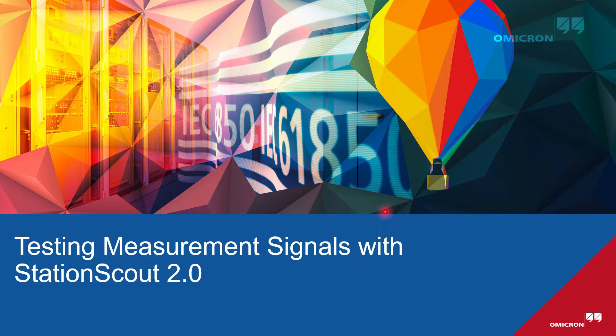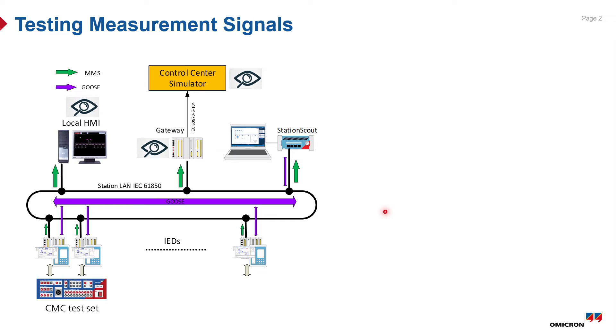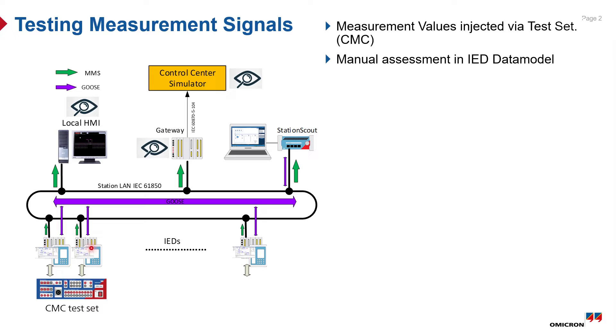First of all, let me explain the setup we are going to use. We have a CMC test set wired to an IED to inject analog measurement values. The measurement values received by the IED are represented in the data model of the IED. We will check if the values injected are matching with the ones in the data model.